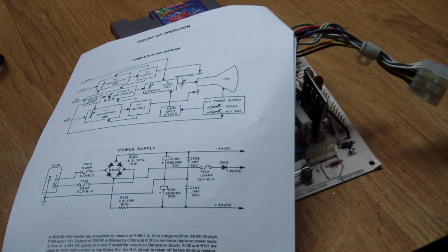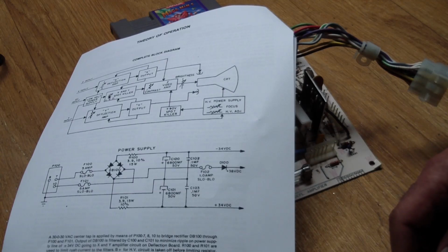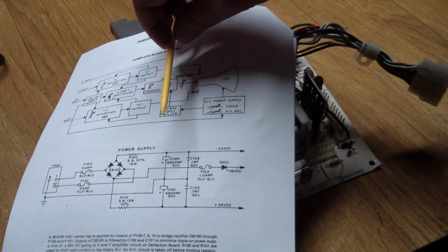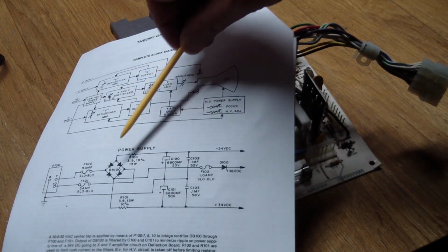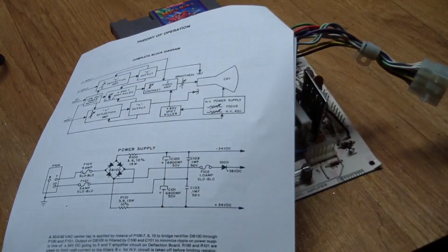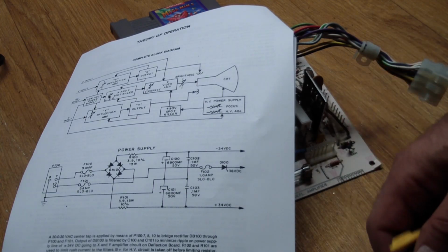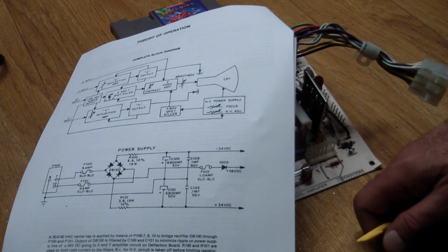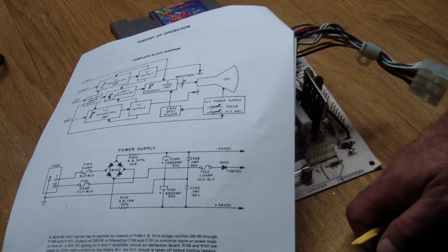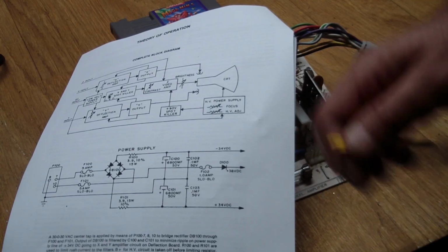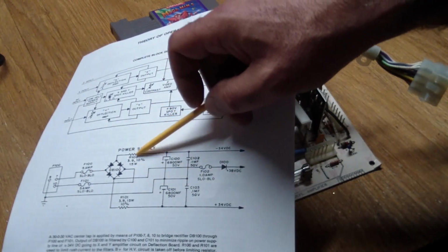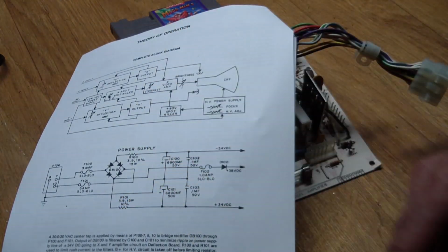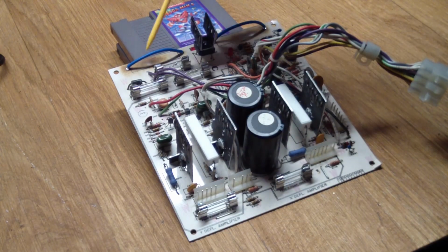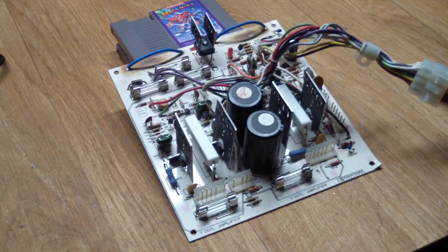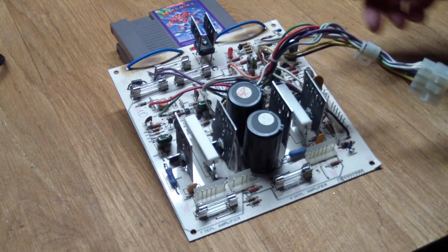And these resistors do commonly fail, even though they're 15 watts. So a better thing to do is basically short them, take them out. Commonly what you do is, if the resistors are still good, leave them in there, but if they're starting to drift in value or they're bad, take them out, always in pairs. Don't leave one resistor in and put a short on the other side - leave things balanced. That's the reasoning behind me using heavy gauge wire to short that and make sure that we're getting power, that the main power source is coming in.